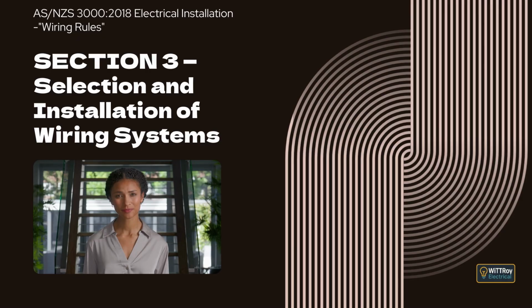Clause 3.5.2, Neutral conductor. This clause explains how the minimum size of a neutral conductor is determined. For a single-phase 2-wire circuit, the neutral conductor or conductors must have a current carrying capacity that is not less than that of the associated active conductor, or not less than the total current to be carried where more than one active conductor is present. For multiphase circuits, the neutral conductor must be sized so its current carrying capacity is not less than the value determined by the expected loading conditions.